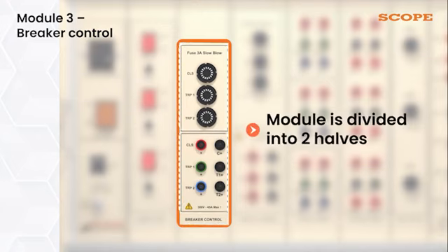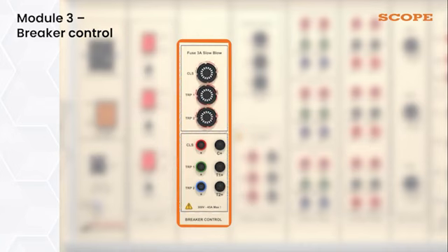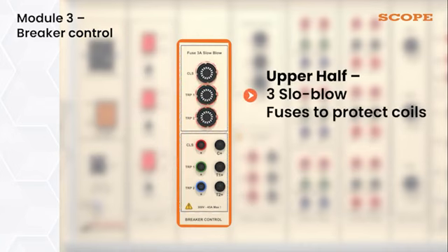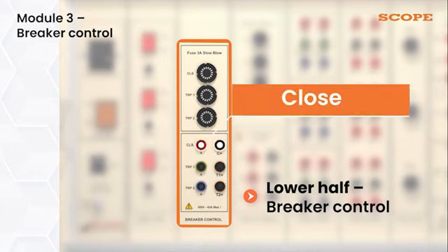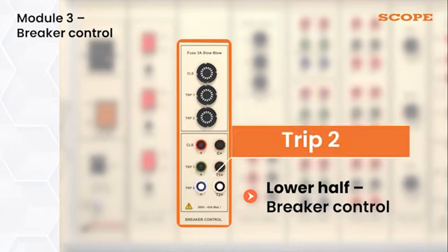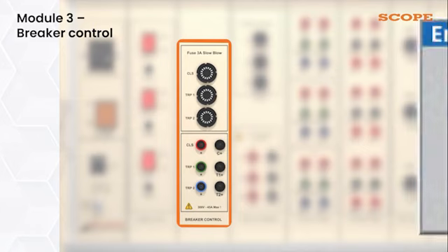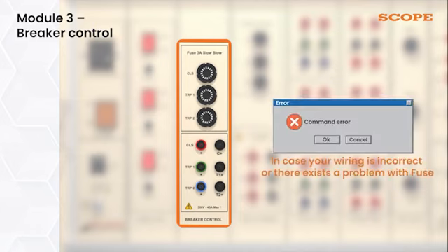We can see that module is divided into 2 halves. Upper half consists of 3 slow blow fuses to protect coils. Lower half consists of breaker control of close, trip 1, trip 2. In software, you would get a command error in case your wiring is incorrect or there exists a problem with the fuse.